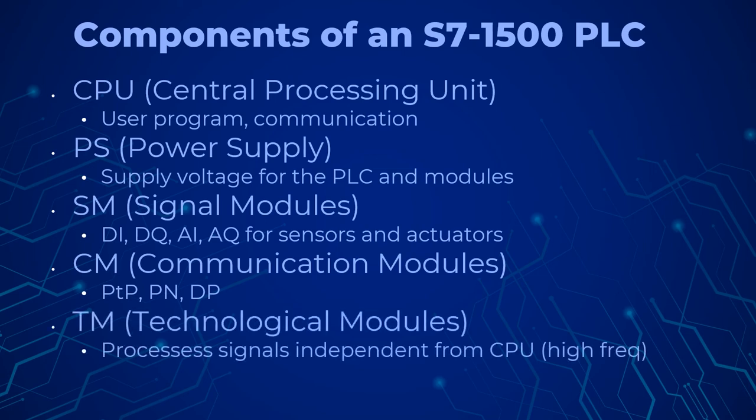Technology modules are signal pre-processing, intelligent I/O modules which prepare and process signals coming from the process independent of the CPU, and either return them directly to the process or make them available at the CPU's internal interface. Technology modules are responsible for handling functions which the CPU cannot usually execute quickly enough, such as counting pulses.